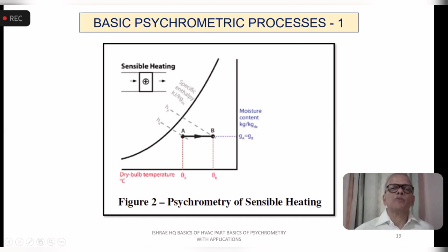Now the basic psychrometric processes. The first process: here you see that we have the sample air at point A, which has this dry bulb temperature and this enthalpy level. In the sensible heating process, we are adding sensible heat. There is no change in the moisture content; it remains unchanged, so it moves along the horizontal line. The change is only in the dry bulb temperature, and that's how it is shown. That is the apparatus we are talking about. The symbol inside is a plus, which means addition of heat. The arrow shows the air movement over the apparatus, with the inlet and the outlet. Temperature is increasing, which is the sensible heating process.